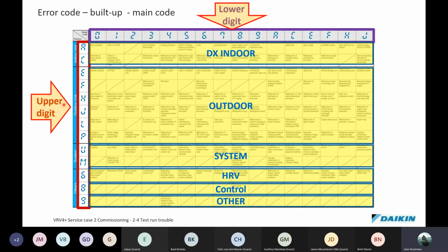Okay, the upper digit. If it falls E, F, H, J, L, and P, any error code beginning with these, you need to start heading towards the outdoor unit. And there's a list of outdoor unit fault codes over there, and again, following the same thing. So if you see code F3, okay, this is malfunction of discharge pipe temperature. Okay, it says malfunction. Now you've got to be careful how you read.